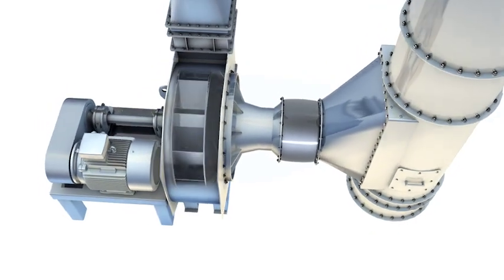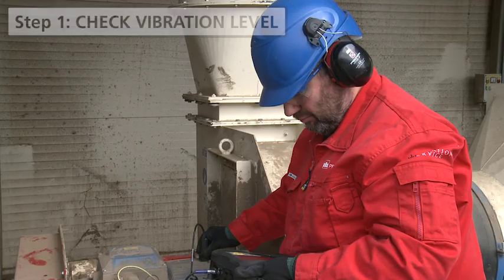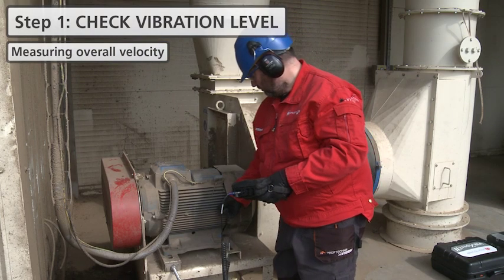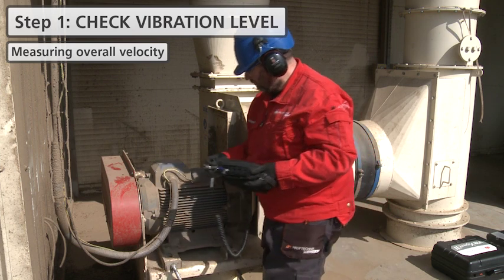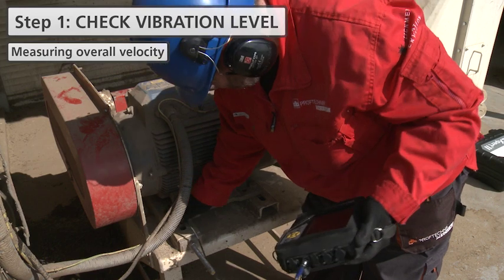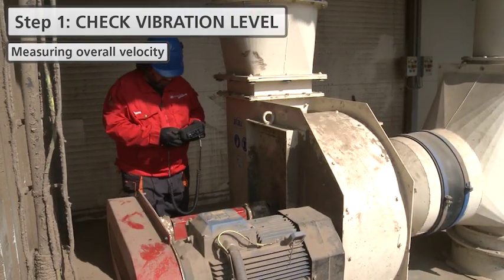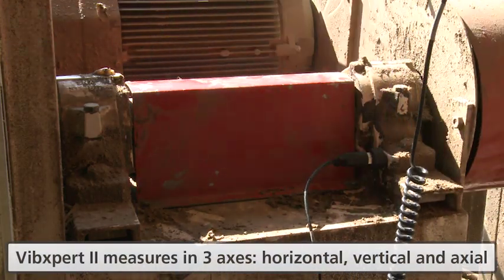A belt-driven motor-fan set is the object of our measurement. The first step is the verification of overall vibration levels on the motor and fan bearings. Vibxpert II measures the vibration in all three axes: horizontal, vertical, and axial.